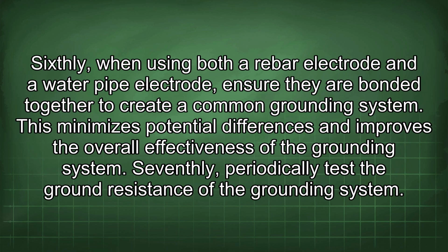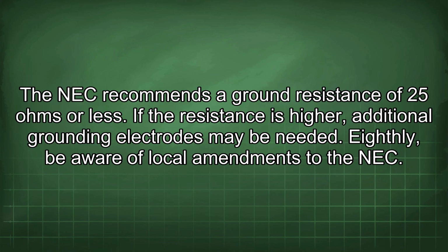Sixthly, when using both the rebar electrode and a water pipe electrode, ensure they are bonded together to create a common grounding system. This minimizes potential differences and improves the overall effectiveness of the grounding system. Seventhly, periodically test the ground resistance of the grounding system. The NEC recommends a ground resistance of 25 ohms or less. If the resistance is higher, additional grounding electrodes may be needed.